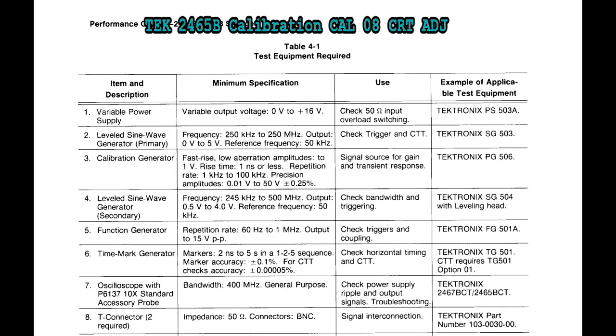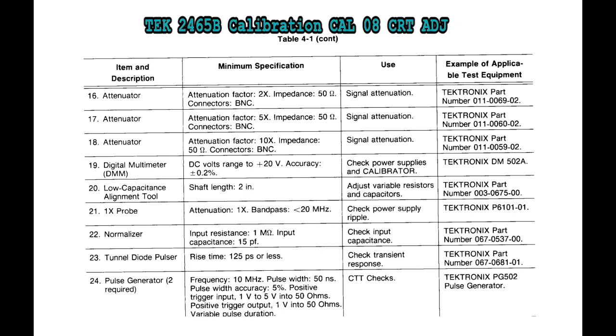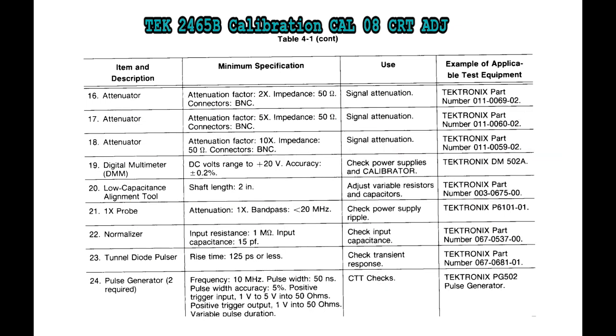The other thing is make sure you have the right calibration equipment. You don't have to use the called out equipment like in here, because most modern equipment will easily meet those standards. But the thing is, you have to have the equipment, and that's what this procedure is about. I use substitute equipment rather than using the called out equipment, because my shop didn't have that older equipment. It's good equipment, it's just that there's more modern equipment out there. So let's go ahead and get to it.